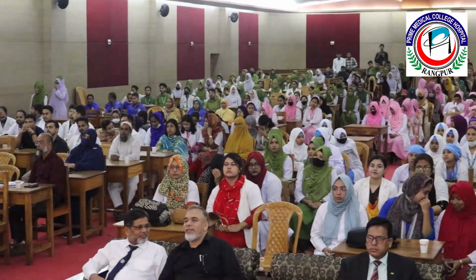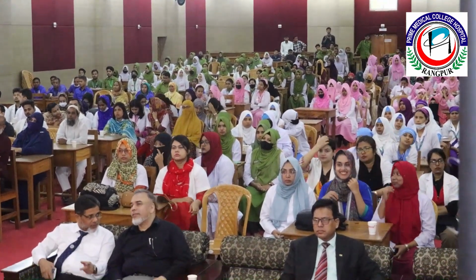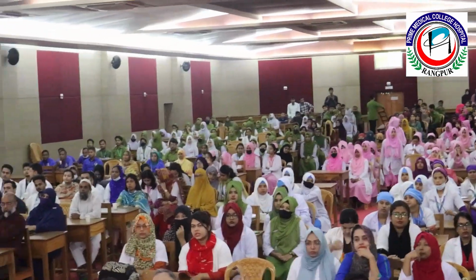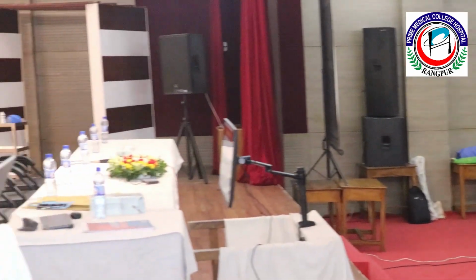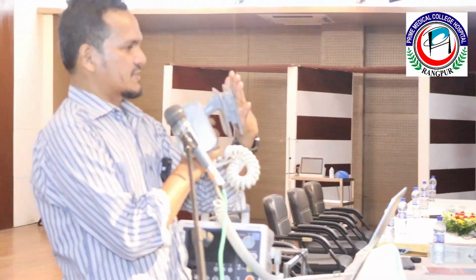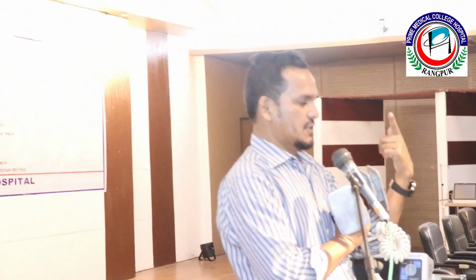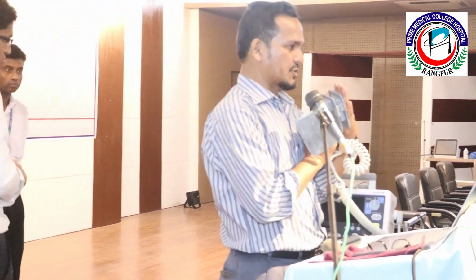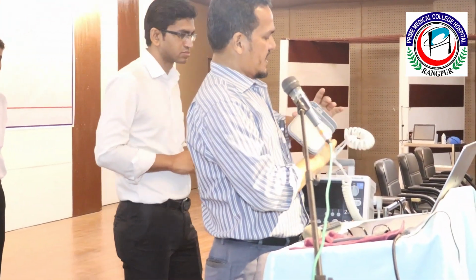Look, we talked about the determinants for successful defibrillation. These are the adult paddles, and these are the contact surfaces. Look, the sixth point: surface area of the shock electrode. This is the adult paddle, and we can change it to the pediatric paddle.